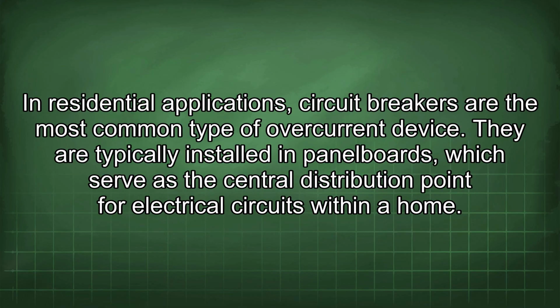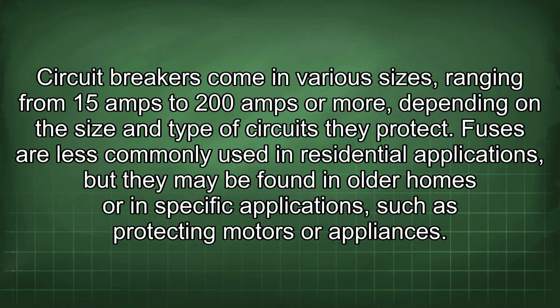In residential applications, circuit breakers are the most common type of overcurrent device. They are typically installed in panel boards, which serve as the central distribution point for electrical circuits within a home. Circuit breakers come in various sizes, ranging from 15 amps to 200 amps or more, depending on the size and type of circuits they protect. Fuses are less commonly used in residential applications, but they may be found in older homes or in specific applications, such as protecting motors or appliances.